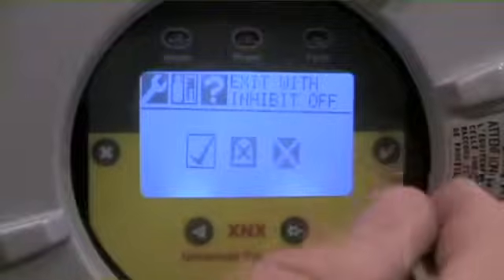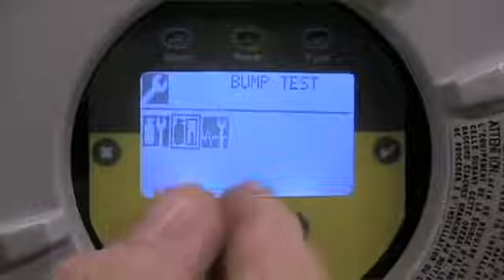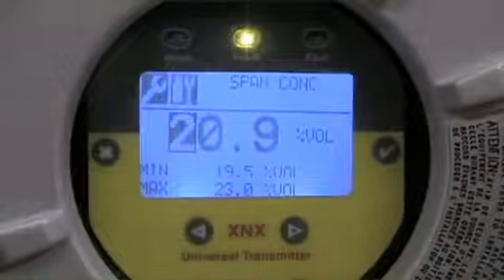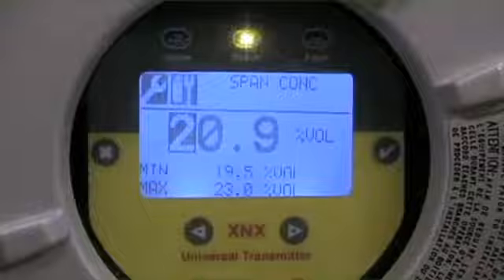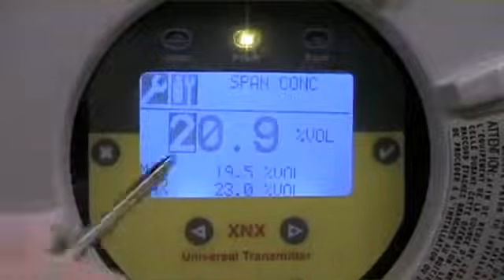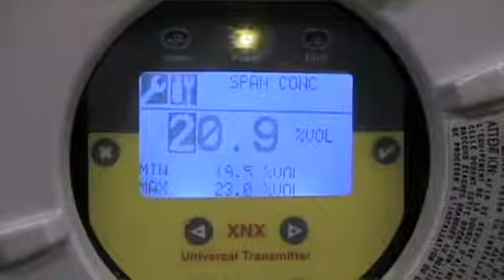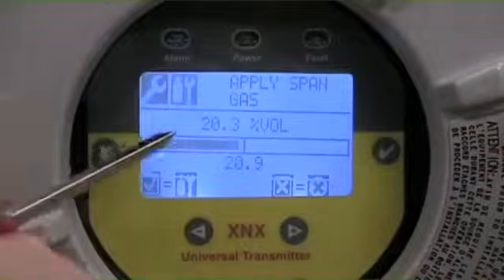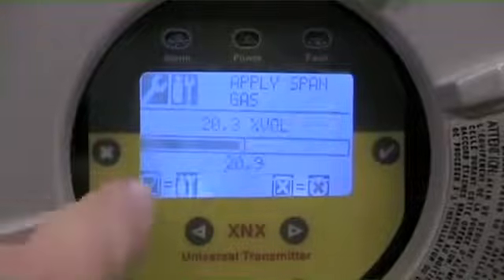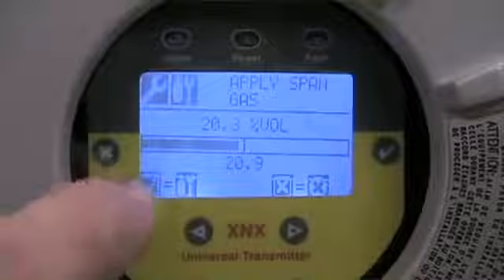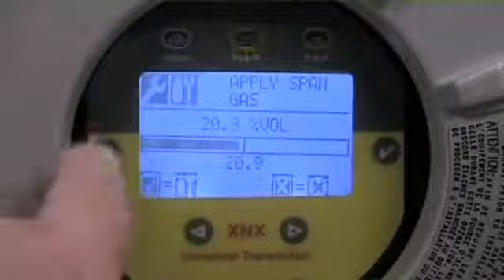In the case of a calibration, we would go back, if we wanted to change something, let's say, we'd enter in the calibration menu. Calibration menu, again, enter. In this case, we're going to tell it what our span gas is. Our default is 20.9. The acceptable ranges, you can see, are listed, minimum and maximum. So I put in the concentration that's on my calibration gas cylinder, enter that value. I'm going to calibrate this on ambient air. You enter this function. The instrument tells you to apply span gas. As you've got your gas flowing into your sensor, there's the check mark that says, yep, I'm ready. The X would be exiting, or I want to bypass this. So I'll go ahead and accept it.